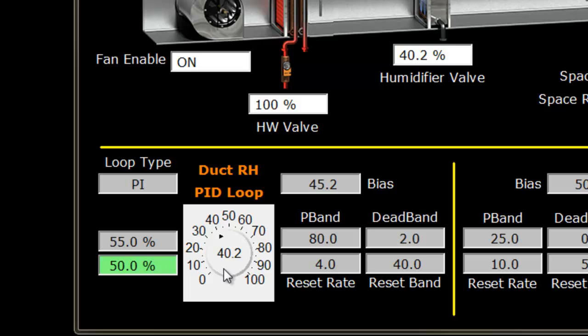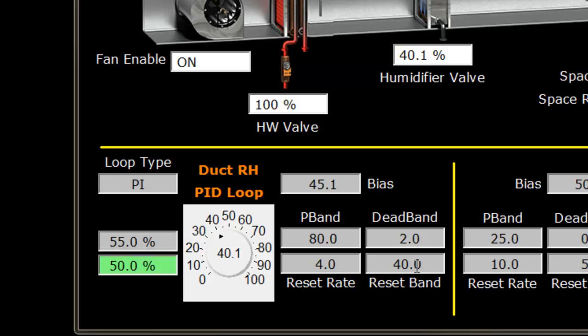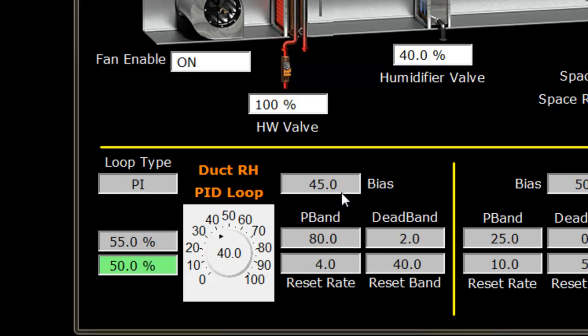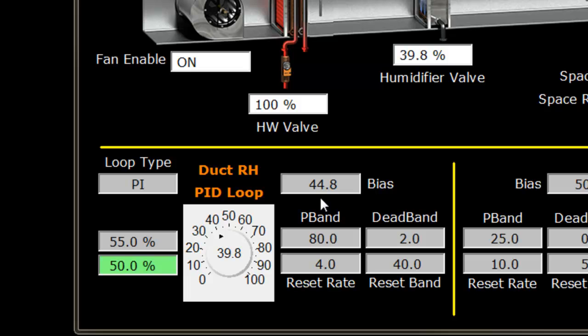The reason is because of that sliding scale. We're only 5% away from set point, and we're saying half of 40 is 20, so we're only a quarter of the full effect. It should be about 1% every minute. Since we've been talking about 4-5 minutes, the 1% per minute has diminished it down to 45.